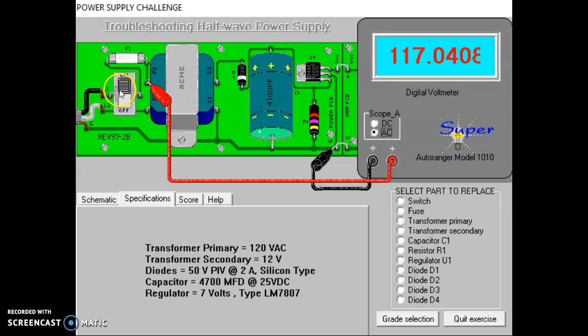That means my fuse is good, it also means my switch is good. If this read 0, we would back up and go to the other side of the fuse, and if we got our voltage then the fuse would be the problem. If we end up having to go to the other side of the switch, then obviously our switch was the problem. In this case, we're good.